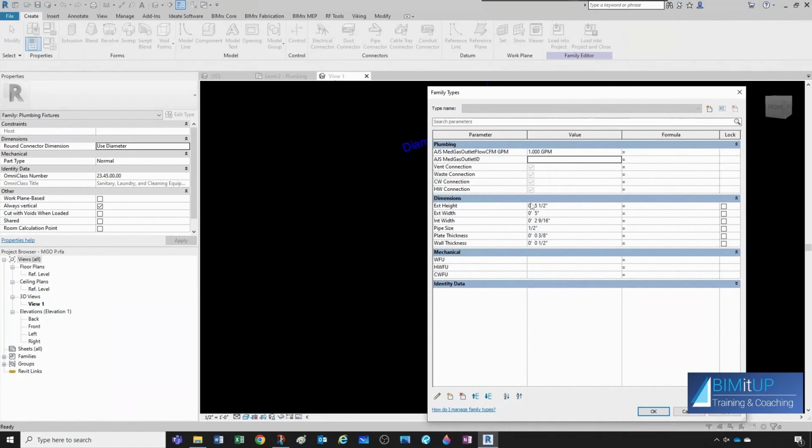And since this one's the positive pressure, I'm going to go ahead and add 3. One of them is going to be oxygen, and that one's going to have the outlet ID OX by default. Let's create another one, medical air. That one's going to have MA. That one's going to have CO2.